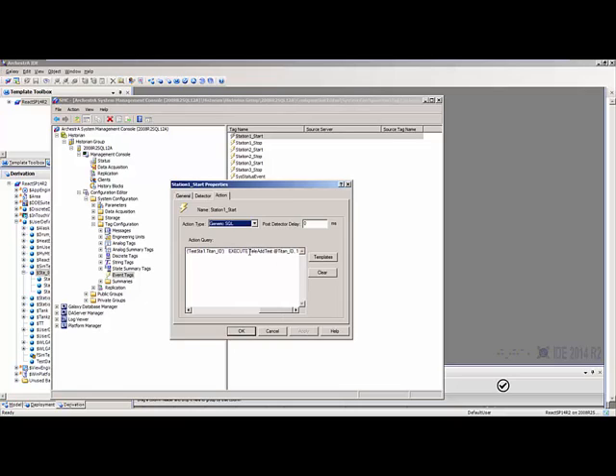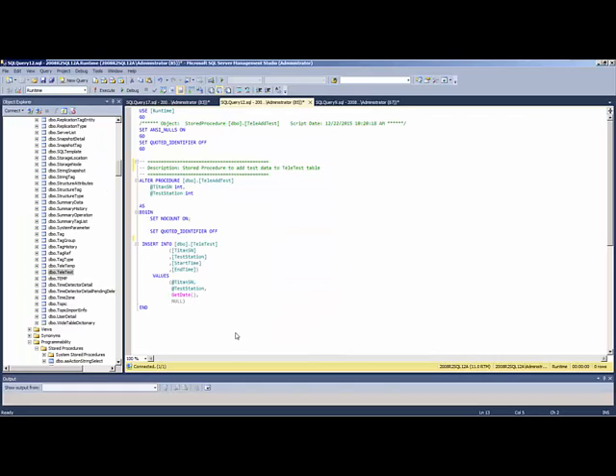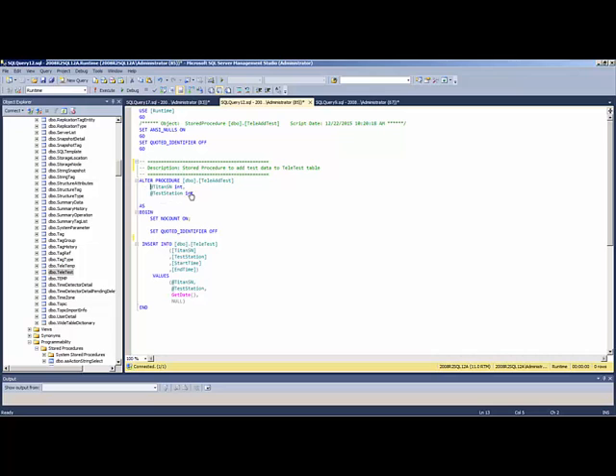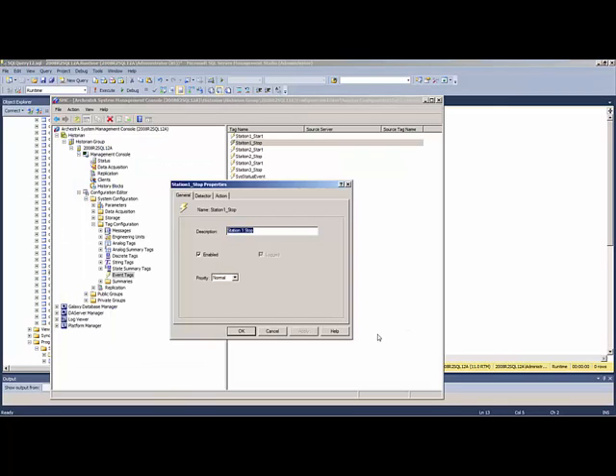It's going to execute a stored procedure that adds that information into the table we previously looked at. Back in SQL Server Management Studio, this is the stored procedure being called by the Wonderware event system. We're passing in the Titan serial number and the test station ID. Basically this is the insert into that table — it's passing in that information and getting the start time, which is the current time, and inserting that into the SQL table.